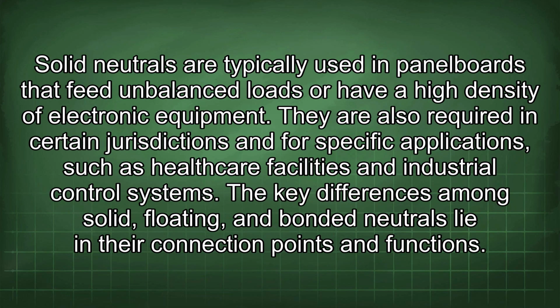Solid neutrals are typically used in panel boards that feed unbalanced loads or have a high density of electronic equipment. They are also required in certain jurisdictions and for specific applications, such as healthcare facilities and industrial control systems. The key differences among solid, floating, and bonded neutrals lie in their connection points and functions.